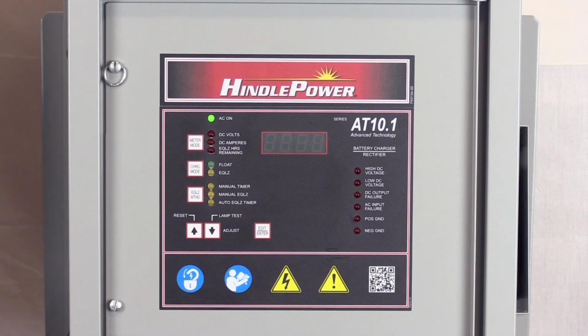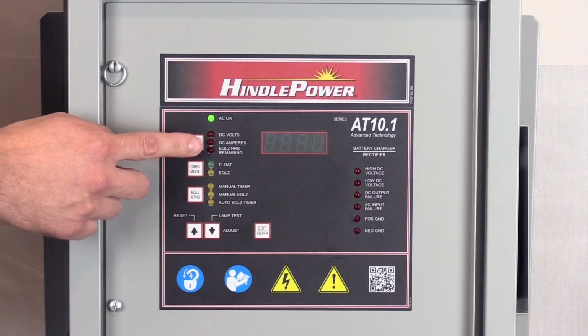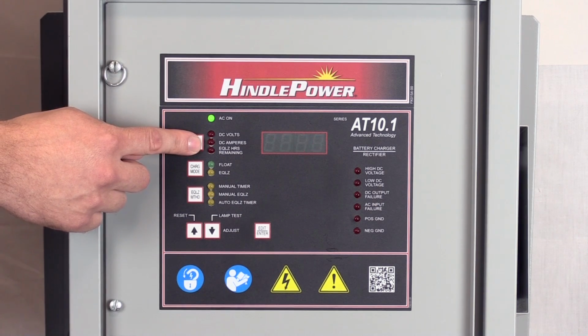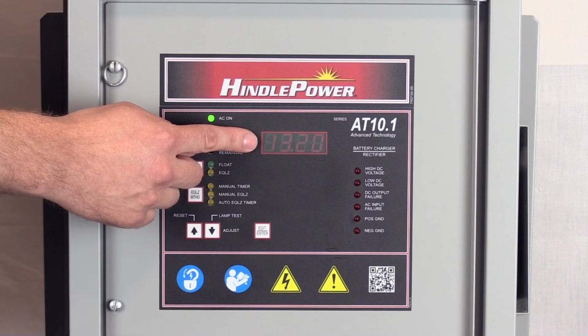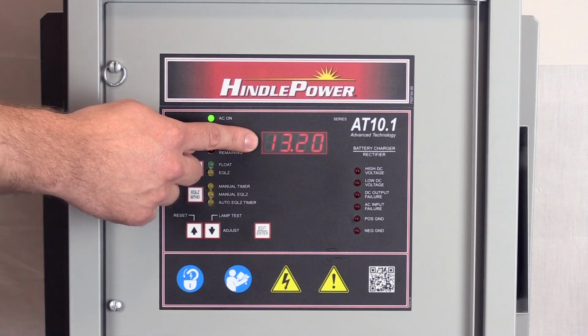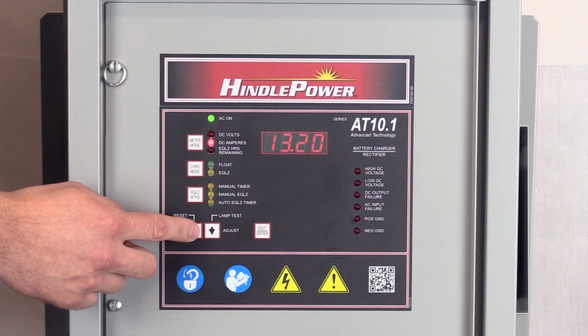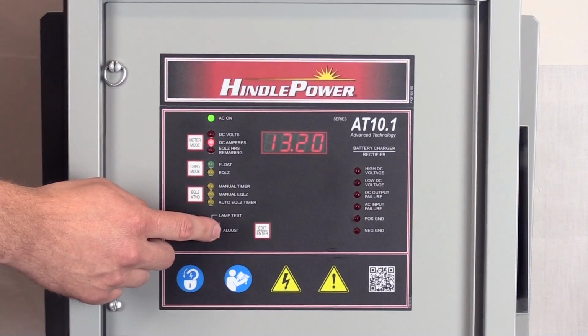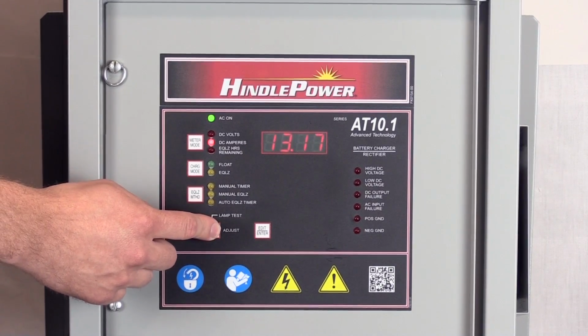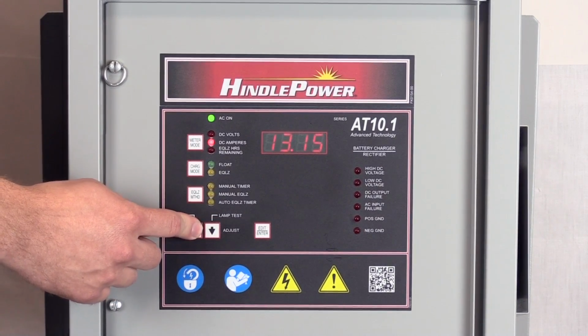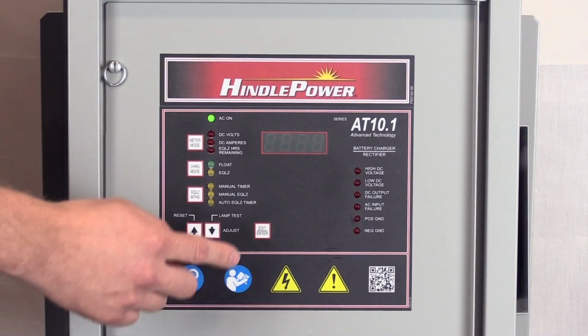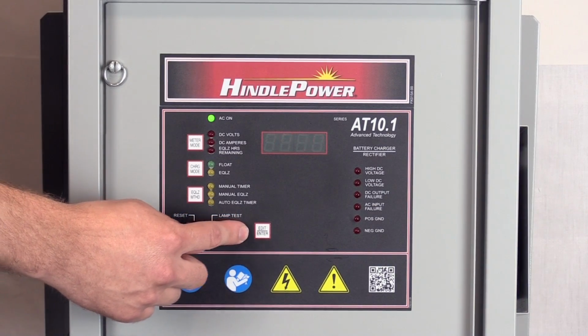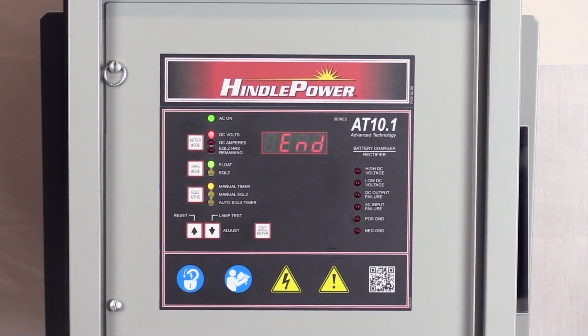The final parameter is the current limit. The red DC amps LED will flash, and the LED display will flash the limit settings. Press the up and down arrow keys to adjust the set point. Press the Edit Enter key. The display will flash end, and now all your parameters are saved.